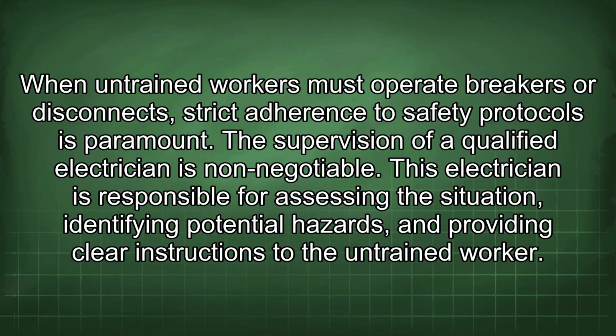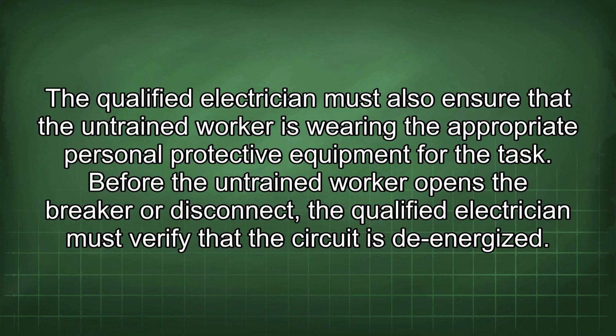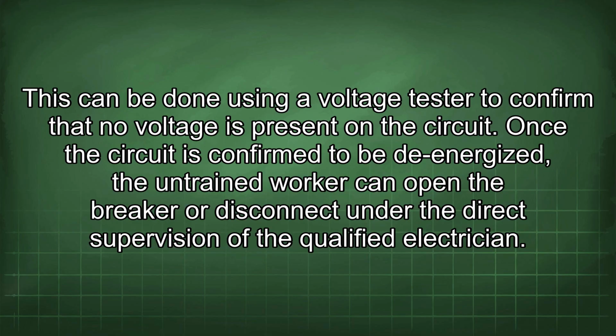This electrician is responsible for assessing the situation, identifying potential hazards, and providing clear instructions to the untrained worker. The qualified electrician must also ensure that the untrained worker is wearing the appropriate personal protective equipment for the task. Before the untrained worker opens the breaker or disconnect, the qualified electrician must verify that the circuit is de-energized. This can be done using a voltage tester to confirm that no voltage is present on the circuit. Once the circuit is confirmed to be de-energized, the untrained worker can open the breaker or disconnect under the direct supervision of the qualified electrician.